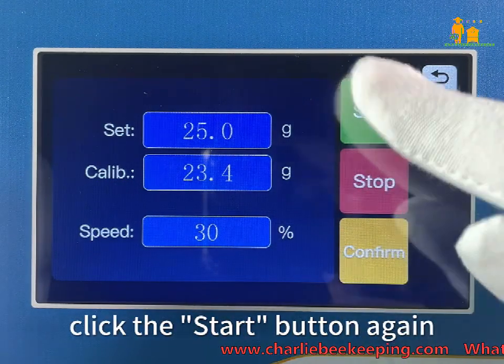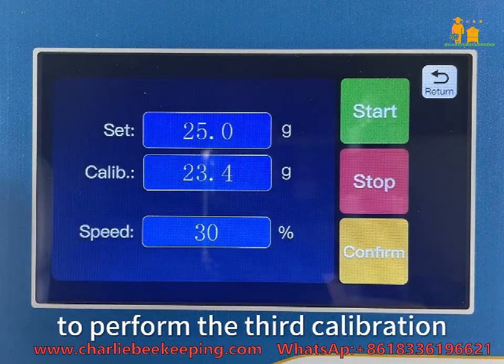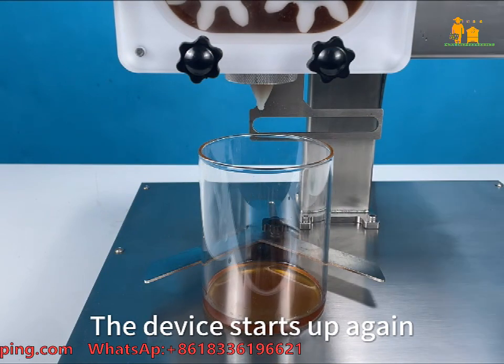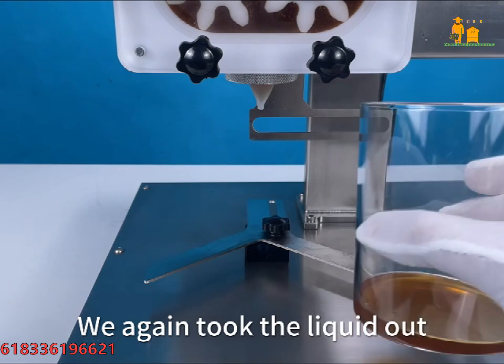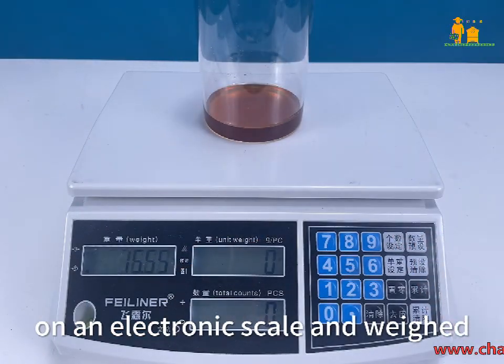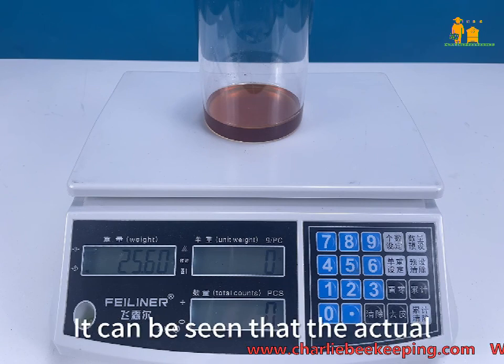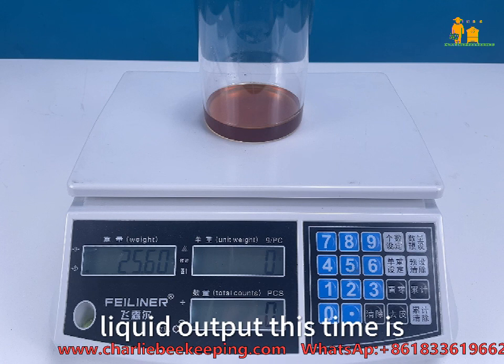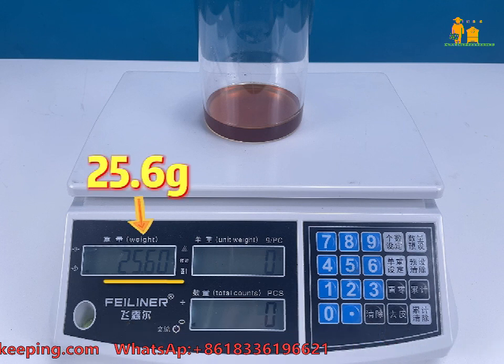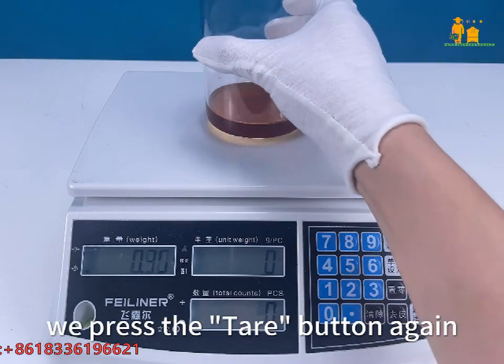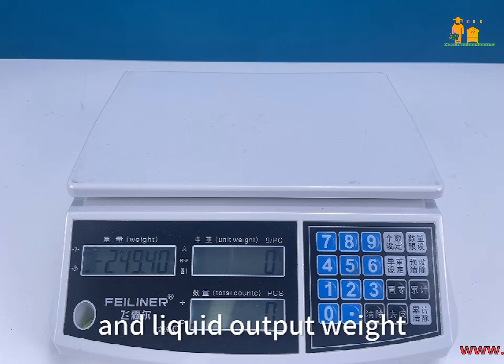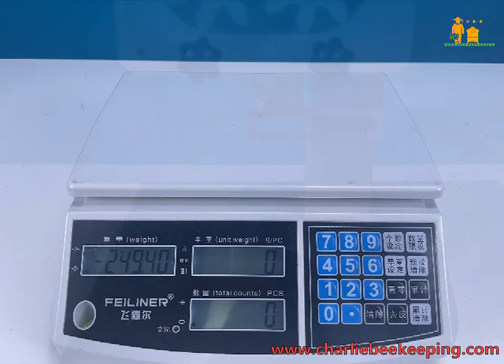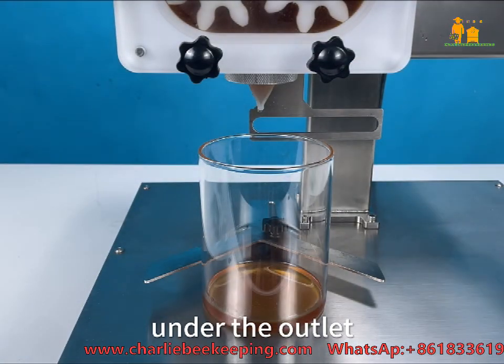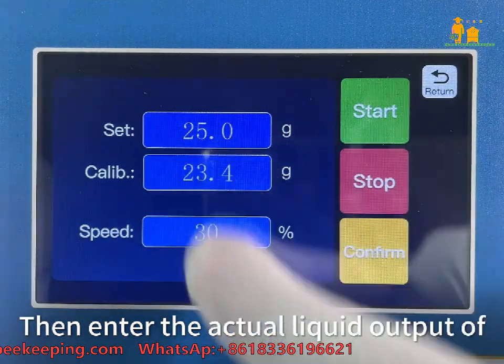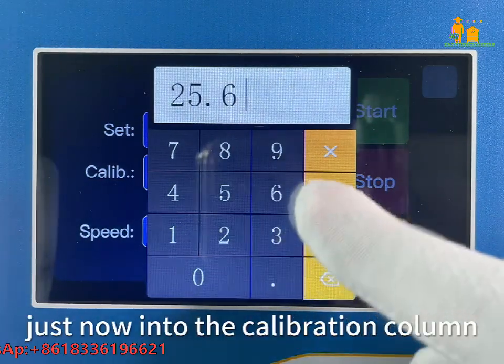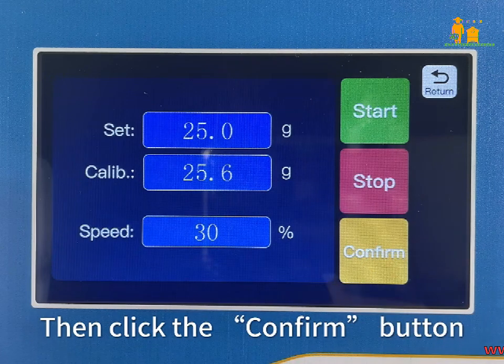At this time, click the Start button again to perform the third calibration. The device starts up again and discharges liquid. We again took the liquid out on an electronic scale and weighed the actual amount of liquid output. It can be seen that the actual liquid output this time is 25.6 gram. At this time, we press the tare button again to remove the bottle and liquid output weight in preparation for the next weighing. We place the bottle again under the outlet. Then enter the actual liquid output of 25.6 gram just now into the calibration column. Then click the Confirm button.